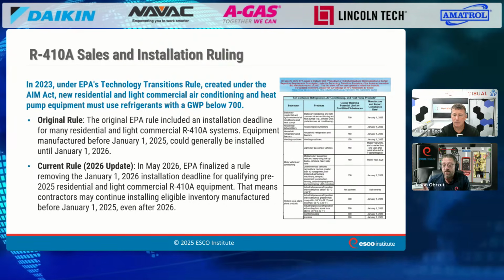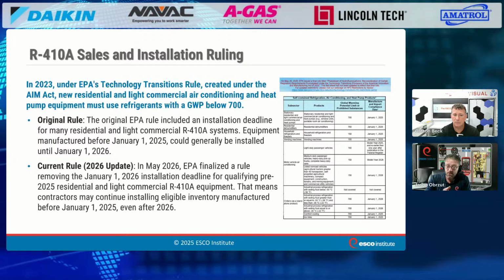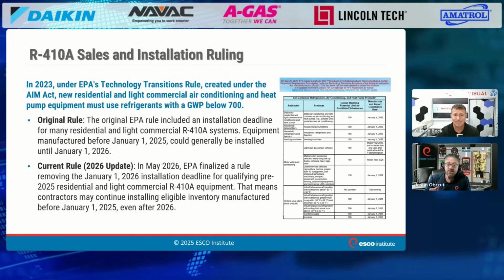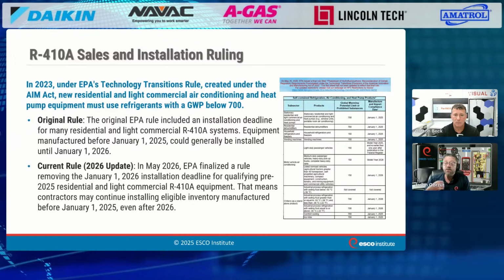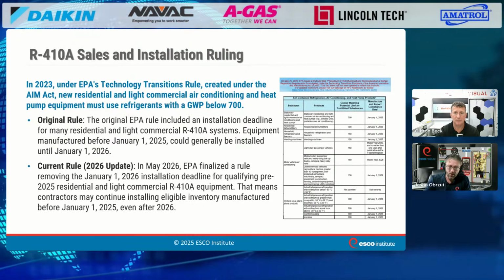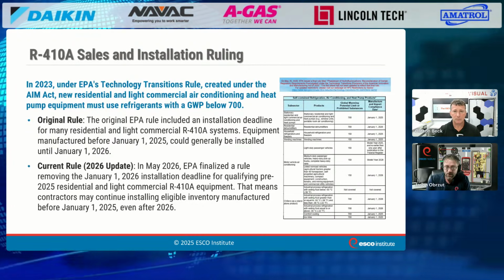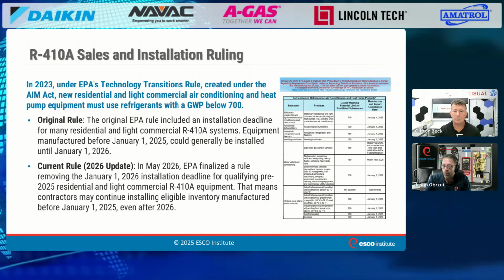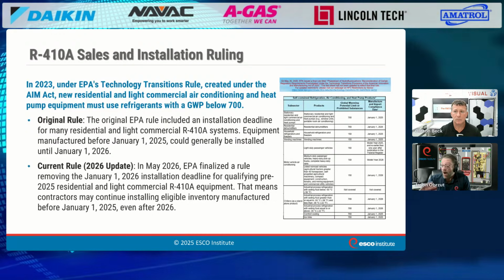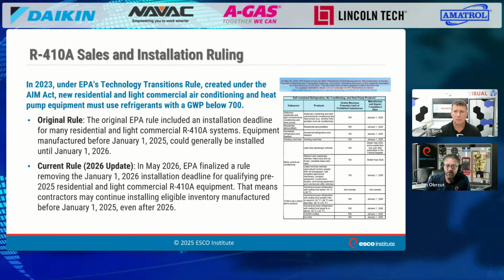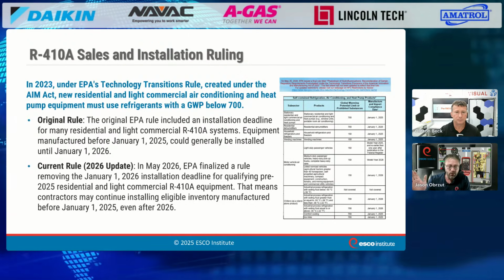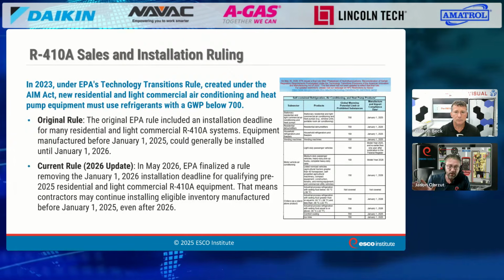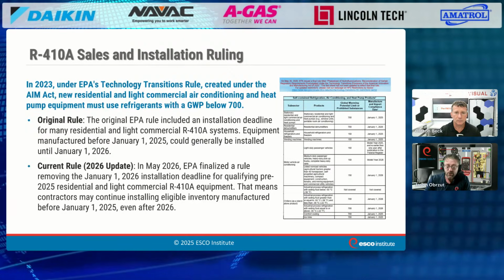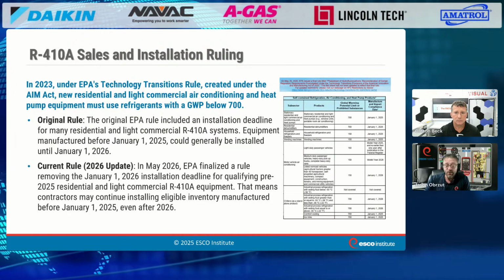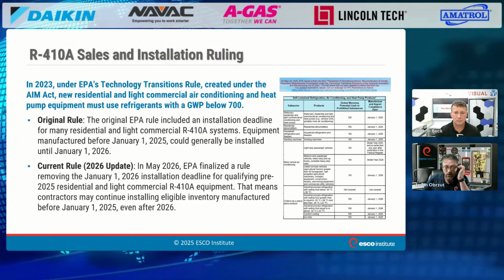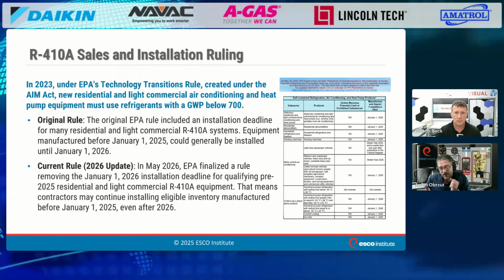It also separates the industry into what we call systems and products. A system is something where we as the technician have to finish the installation. We have to run the line set and we finalize the charge, right? We top it off, do the superheat, subcooling or weigh in, whatever we're doing. A product is something that is finished when it leaves the factory. Think of a package unit, rooftop unit, window unit. It is completely finished. The charge and the refrigerant circuit are complete when it leaves the factory. So that is the difference, as far as this rule is concerned, between a product and a system.